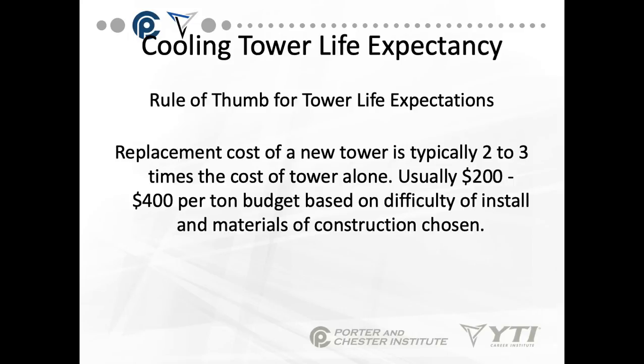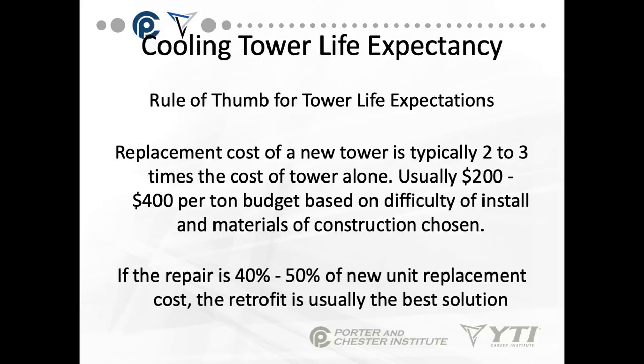So replacement cost of a new tower is typically 2 to 3 times the cost of the tower alone. Usually $200 to $400 per ton budget, based on the difficulty of installation and the materials of construction chosen. If the repair is 40 to 50% of a new unit replacement cost, the retrofit is usually the best solution.